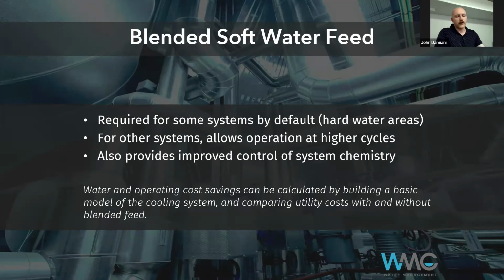Because if you cycle up water, let's use Great Lakes water as an example, Toronto, you're going to find that as you cycle that up, hardness is the first parameter that you hit as a limit. I can't go past 450 to 550 ppm, depending on my temperatures and everything like that, before I start risking precipitating that calcium out and creating scale. The chemistry can only get you so far, but if we remove a lot of that hardness, that gets that parameter out of the way so that we can cycle it up higher. It gives us better control of the system chemistry as well.